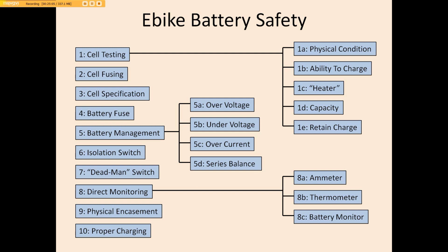If all of your cells are individually fused, then as your healthy cells discharge into that one bad cell, you've got 15 cells all dumping their power into it, and that bad cell is going to experience quite a bit of current. But if you have a fuse on that cell and it blows, suddenly your bad cell is electrically isolated from the rest of the battery, so no more current can go in or out of it. It does its own thing, it catastrophically fails — hopefully it doesn't explode or catch fire — but at least it has a chance now that the fuse has blown. So that's one example of why it's a good idea to put a fuse on each of your cells.